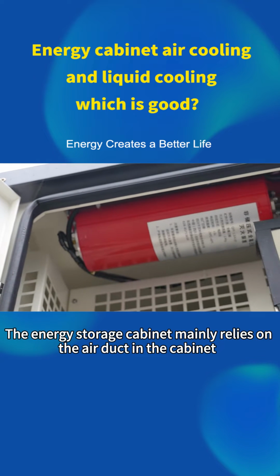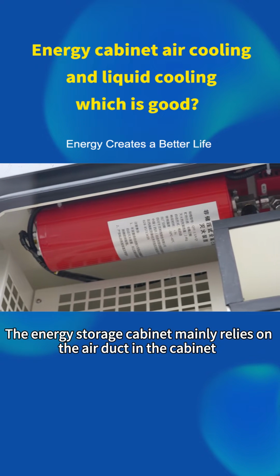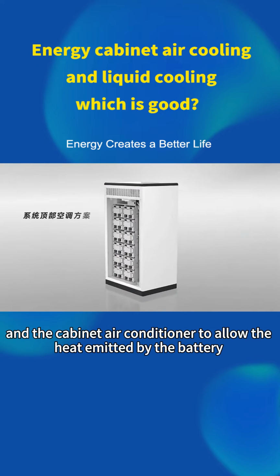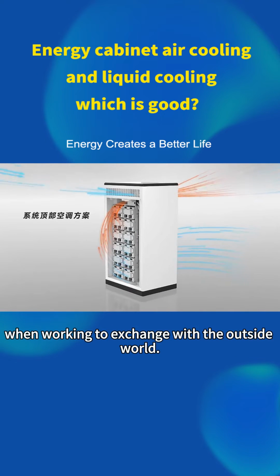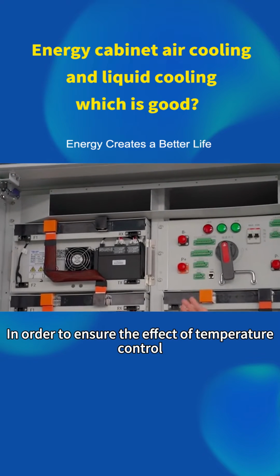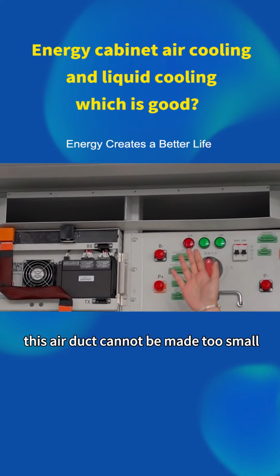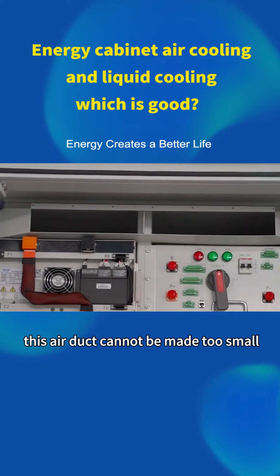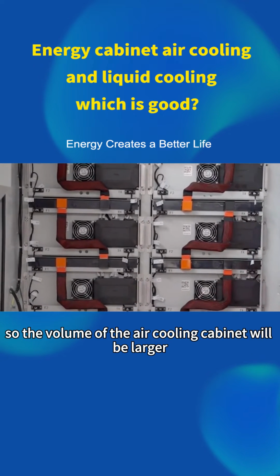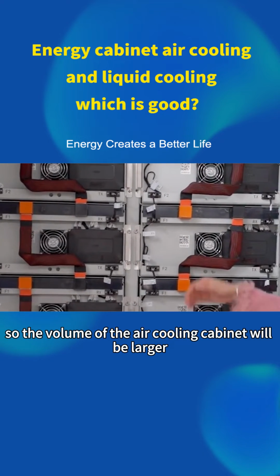The air cooling energy storage cabinet mainly relies on the air duct in the cabinet and the cabinet air conditioner to allow the heat emitted by the battery when working to exchange with the outside world. In order to ensure effective temperature control, this air duct cannot be made too small, so the volume of the air cooling cabinet will be larger.